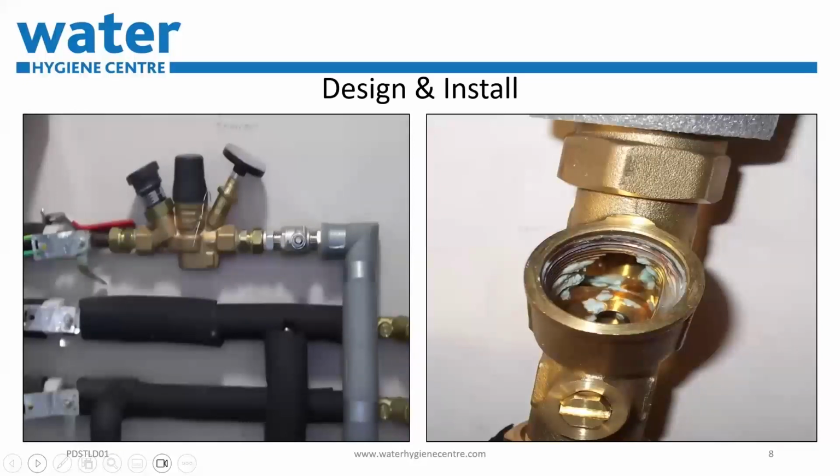Hospital water refurb. 75% of returns were not balanced, circulating. So Pseudomonas aeruginosa and Legionella positives were plenty. The contractor had to come back and put it right two years after the work was completed. The ward was closed for two months. Poor configuration was the issue: position of returns, balancing of the system, strainers and filters had biofilms in them. Who was the culprit? The design and build contractor.